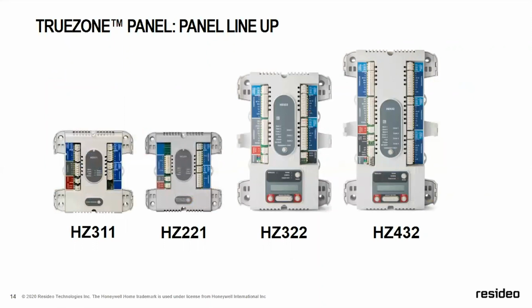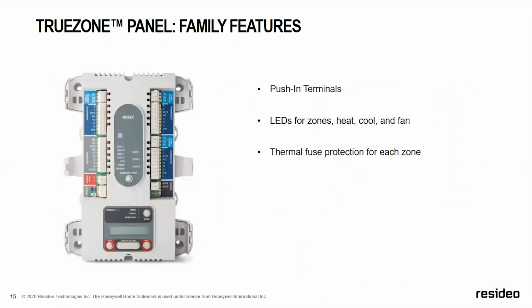Here's our zone panel layout: 311, 221, 322, and the 432. We use push-in terminals, which makes it easier to wire. LEDs for the zones show which zone is on, whether it's calling for heat or cool. We also use thermal protection, which means circuit breakers. I've had a lot of contractors call me up and say, my panel doesn't work because every time zone 1 calls, the panel shuts off. Well, we would go out and find that they had a dead short on that zone. When the zone would call, it would go into protection, so it goes to sleep. When the short is repaired, the zone panel worked perfectly.